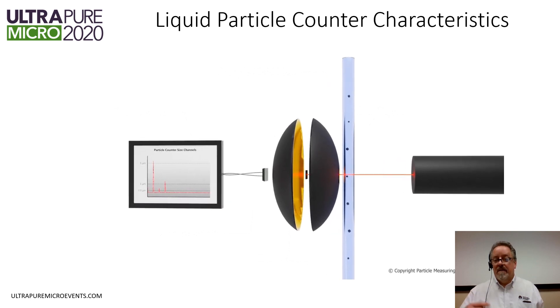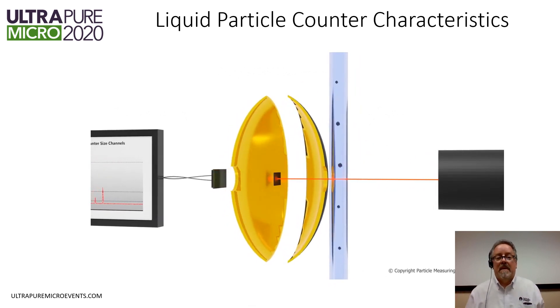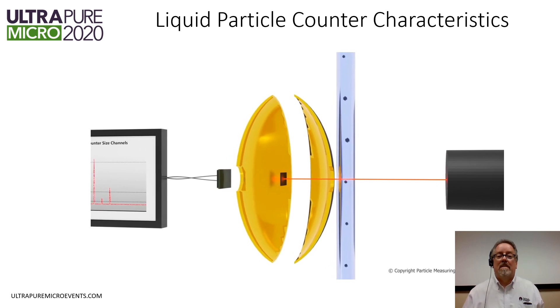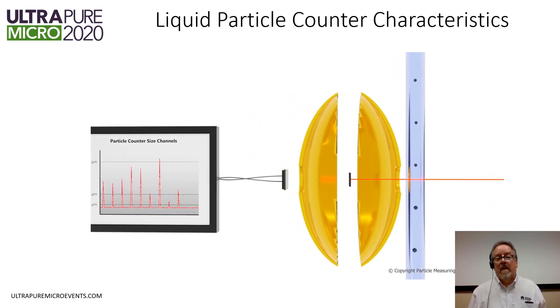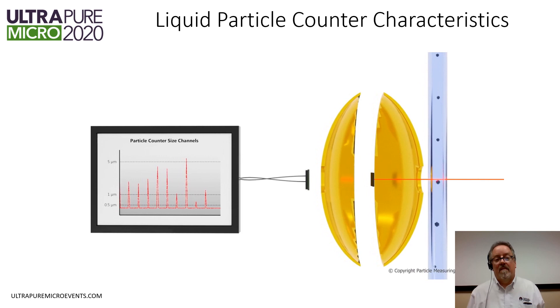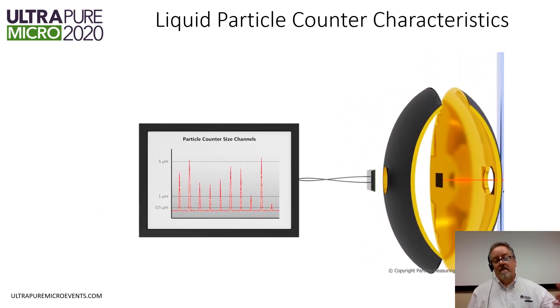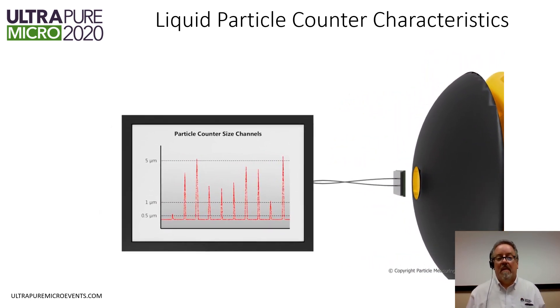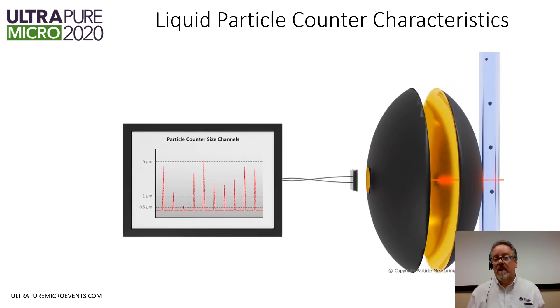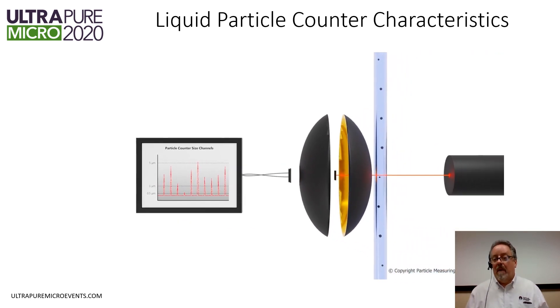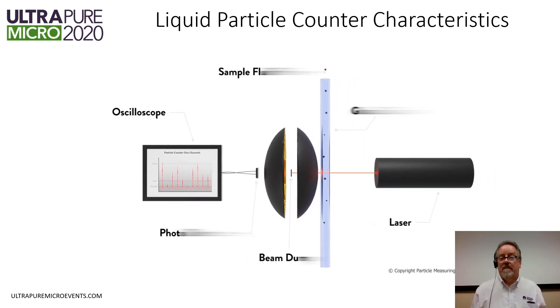As the particles pass through the beam, small particles scatter a little bit of light and create a small signal, while large particles scatter a lot of light and create a bigger signal. You can see that on the left, where the signal in millivolts equivalent is on the vertical scale, and every time a particle passes through it creates a spike in signal. We can bin those by particle size to know how many particles in each size pass through the laser beam.